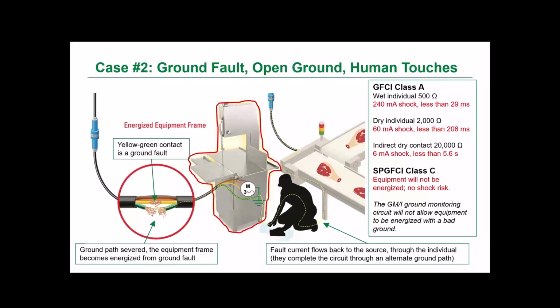Then when the individual comes into contact with that equipment, there is now a path for fault current to flow through the wet floor, through the person, to the frame of another piece of equipment behind them, and then back through the ground conductor on that second piece of equipment to the grounding system. So the Class A GFCI would sense that fault current once that connection is made and trip within that UL 943 mandated trip time. Now what we've shown here, if we use, we'll say a 500 ohm body impedance model for wet contact, this shock could be about 240 milliamps, which when you do the math would be tripped by the GFCI in 29 milliseconds.